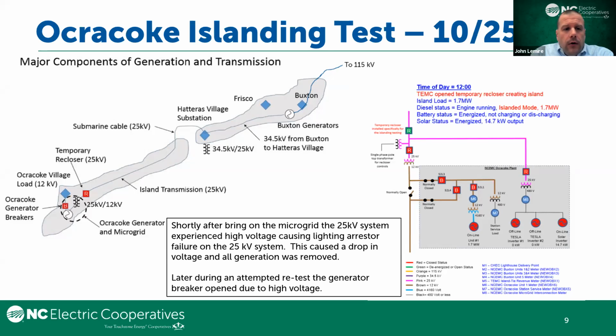and we were successful. Our findings came out about the same time that EPRI and their program came out on effective grounding with inverter-based generation. And what was validating was that what NCEMC experienced was one of the lessons that EPRI came out with in their standardized grounding transformer connections and in the report. So not only did it validate our use case and our issues, but NCEMC standardized our transformer configuration for future microgrids so that we can address the effective grounding and not have these issues again.